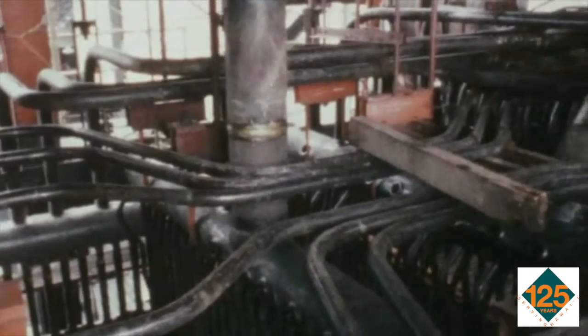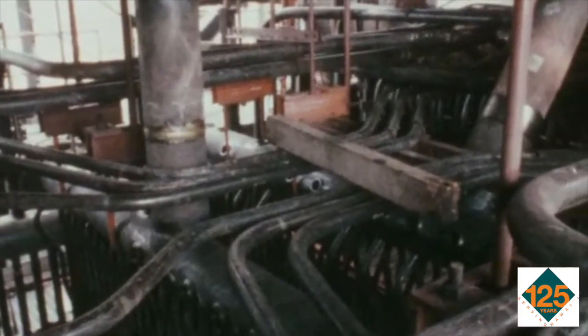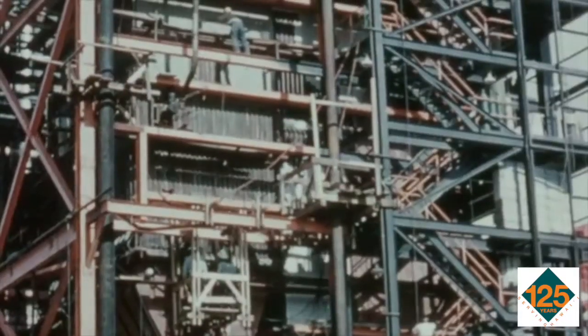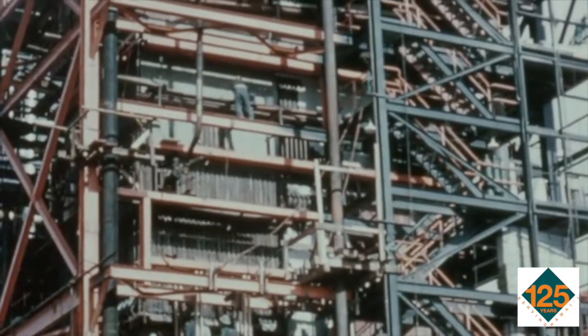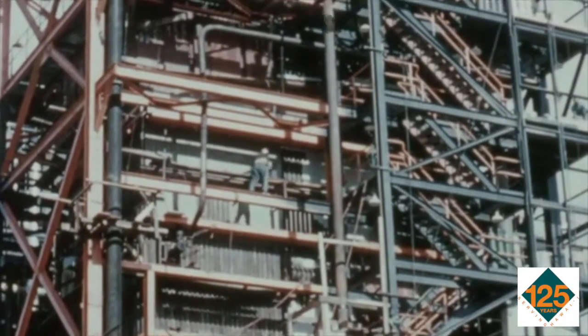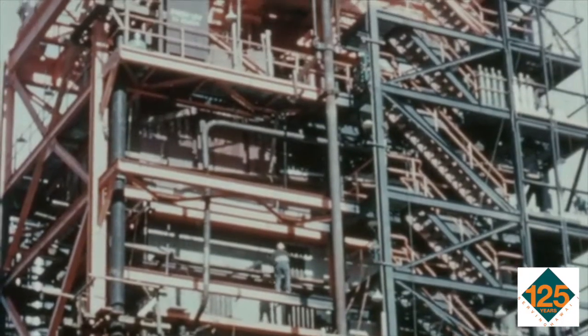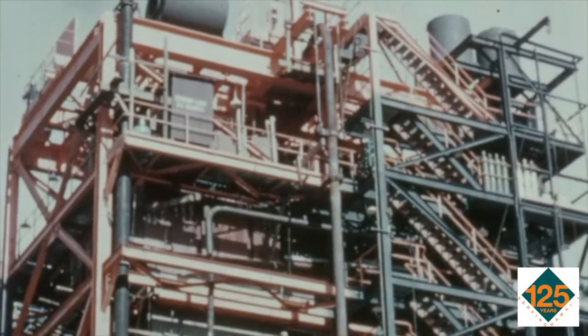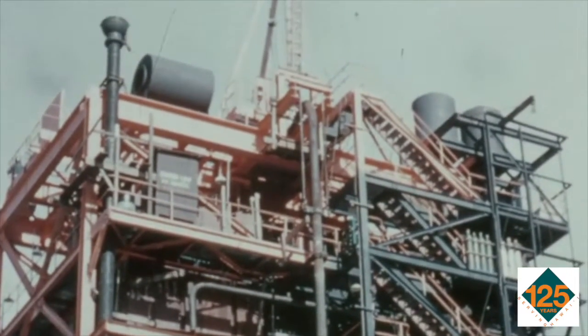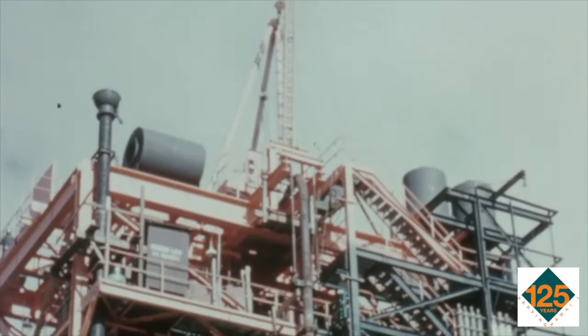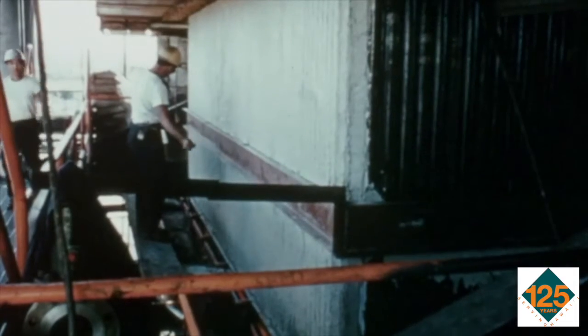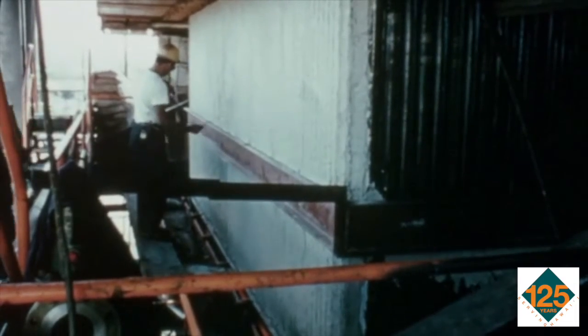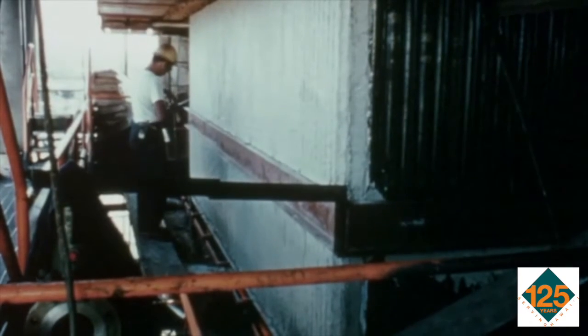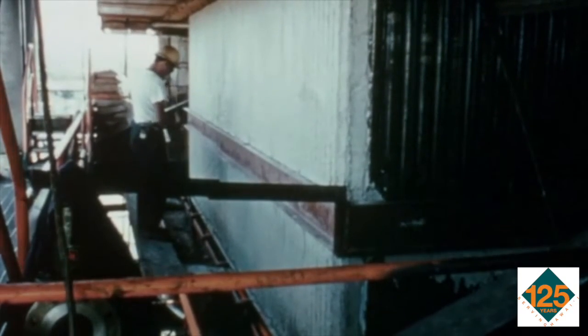Complex piping connects the boiler drum to the furnace walls and superheater sections to provide passages for water and steam through the boiler. After the steam has passed through all elements of the boiler and is at the correct temperature and pressure, the vertical main steam pipe is the outlet. The open spaces between the wall tubes were filled and sealed to withstand internal pressure and the heat in the furnace. A plastic material covers the finished boiler to provide a weatherproof coating.